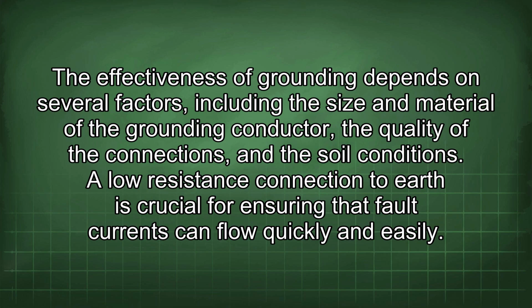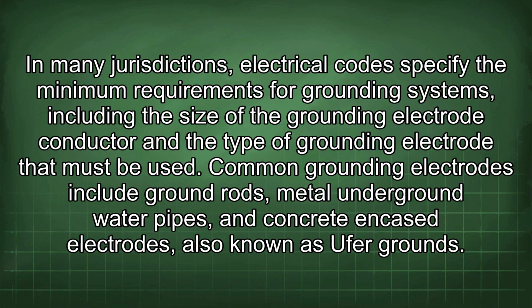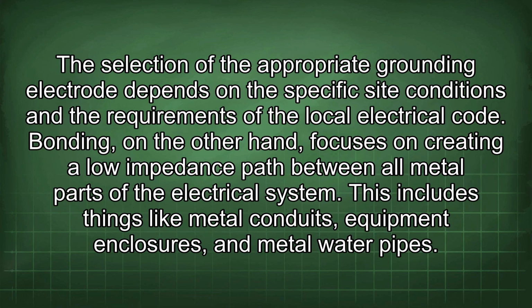A low resistance connection to earth is crucial for ensuring that fault currents can flow quickly and easily. In many jurisdictions, electrical codes specify the minimum requirements for grounding systems, including the size of the grounding electrode conductor and the type of grounding electrode that must be used. Common grounding electrodes include ground rods, metal underground water pipes, and concrete encased electrodes, also known as Ufer grounds.